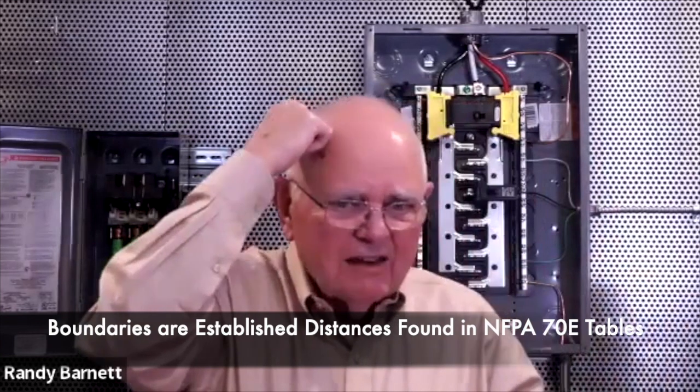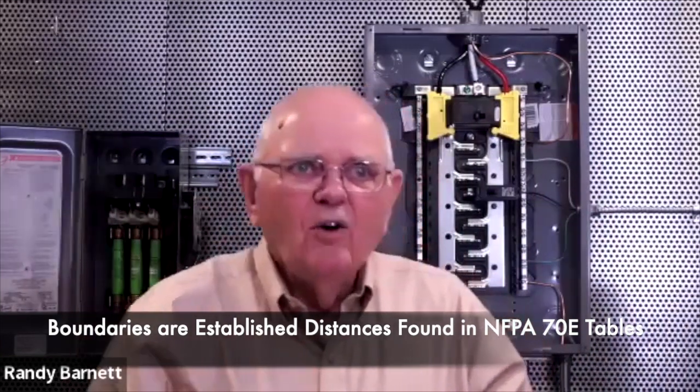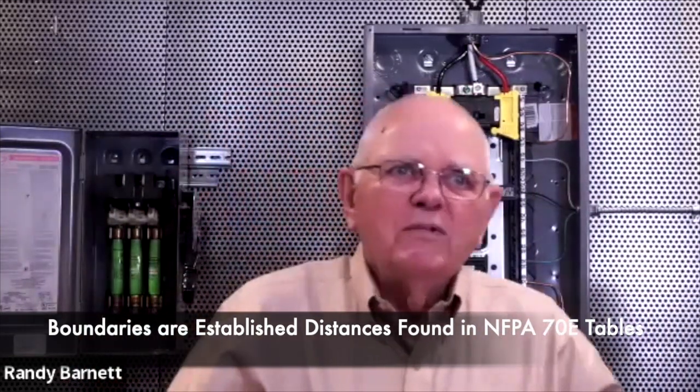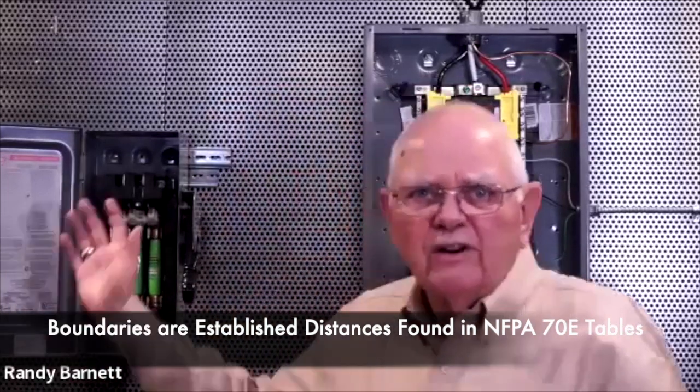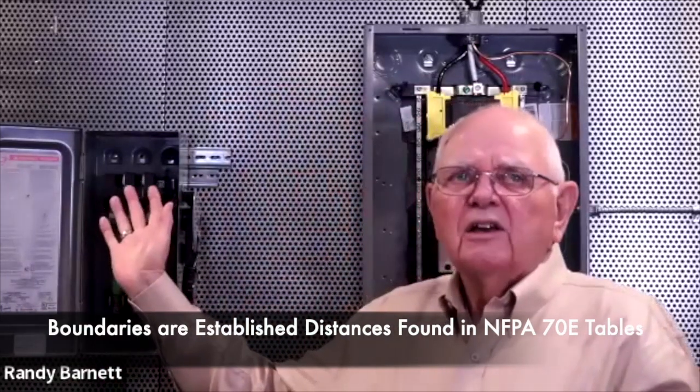Now, boundaries. Boundaries are only right here, okay? I keep boundaries up in my head. I know that the limited approach boundary at 480 volts is going to be 3 feet 6 inches. Now, how do I know that? Because there's a table in the NFPA 70E standard, not the NEC.